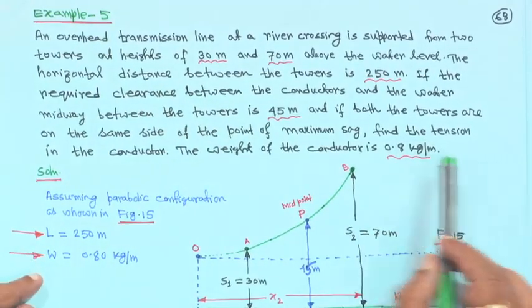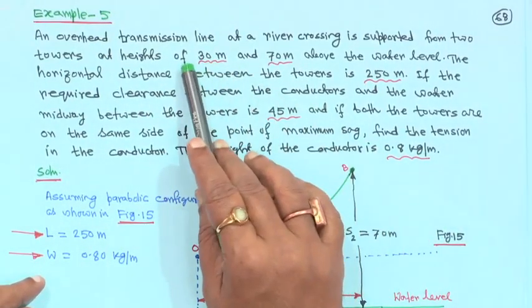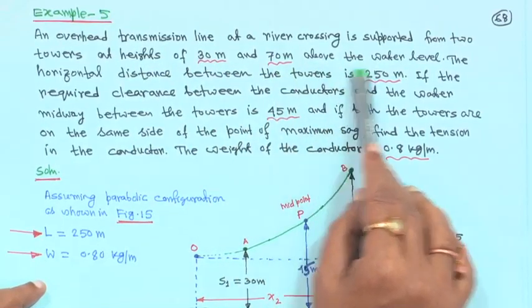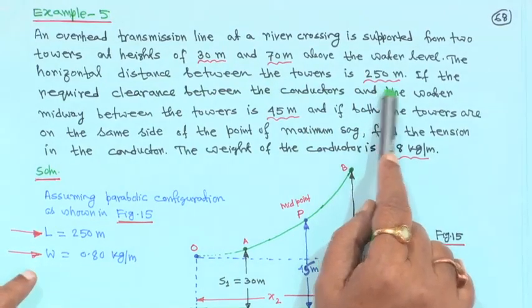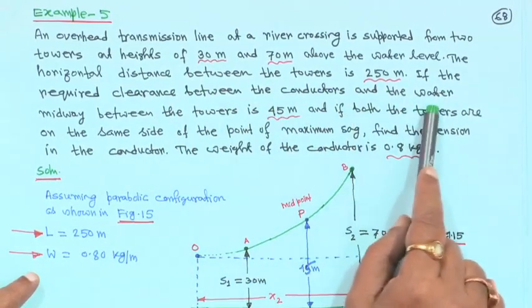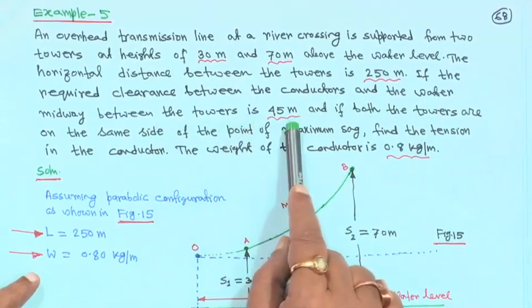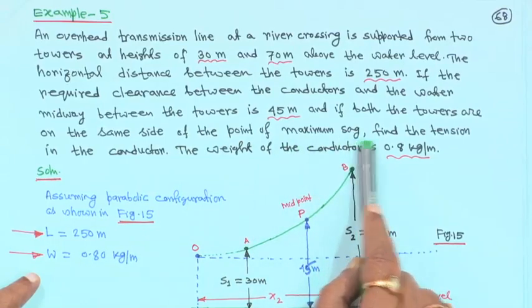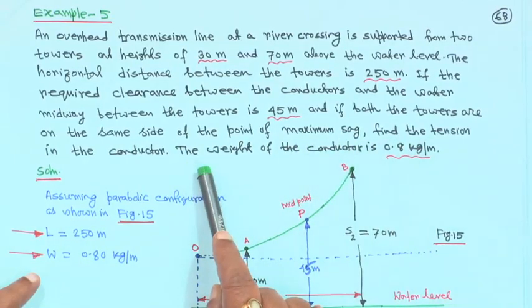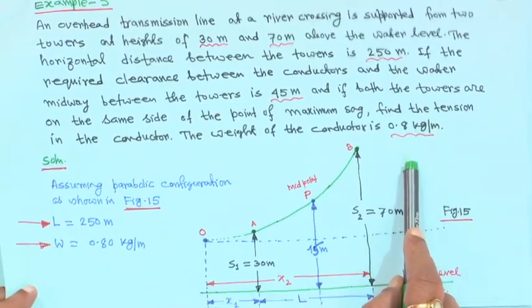So, just now we have seen example 5. Reading the problem once again: an overhead transmission line at a river crossing is supported from 2 towers at heights of 30 meter and 70 meter above the water level. The horizontal distance between the towers is 250 meter. If the required clearance between the conductors and the water midway between the towers is 45 meter, and if both towers are on the same side of the point of maximum sag, find the tension in the conductor. The weight of the conductor is given 0.8 kg per meter.